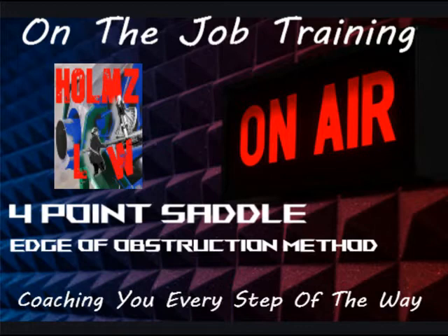All right, and for the second bend, you're simply just going to slide it down to mark B and rotate it 180 degrees. Now your mark A should be in front of you, and so should C and D. You should have no marks behind you now, except for your mark B should be on the arrow. Now you bend it to whatever degree again that you bent your first bend at. All of these bends are going to be at the same degree that you choose.